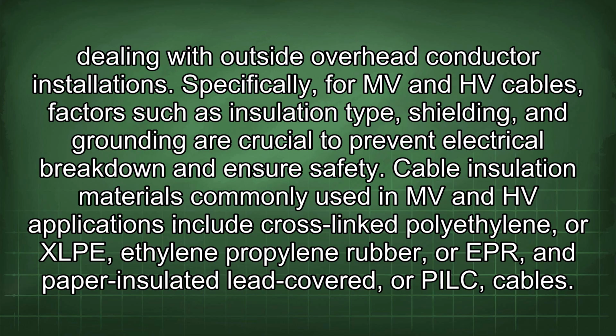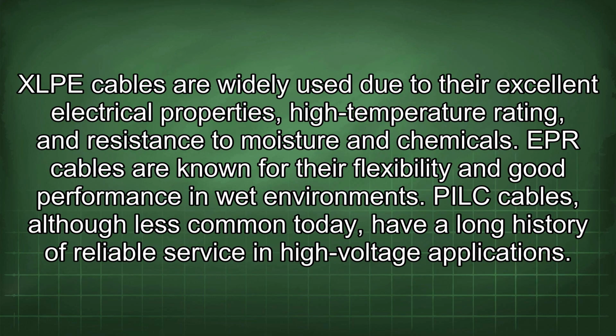Cable insulation materials commonly used in MV and HV applications include cross-linked polyethylene, or XLPE, ethylene propylene rubber, or EPR, and paper-insulated lead-covered, or PILC, cables. XLPE cables are widely used due to their excellent electrical properties, high temperature rating, and resistance to moisture and chemicals. EPR cables are known for their flexibility and good performance in wet environments. PILC cables, although less common today, have a long history of reliable service in high-voltage applications.